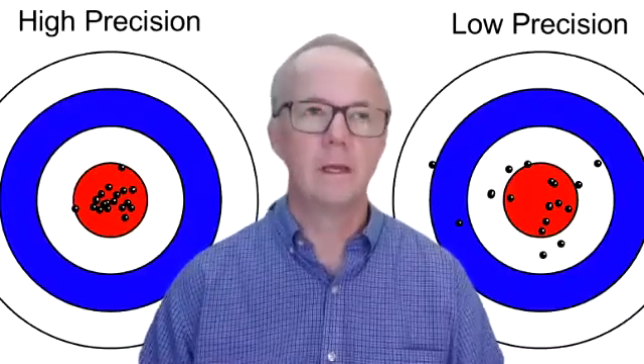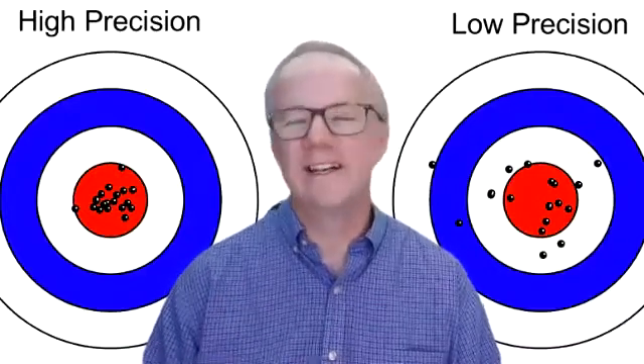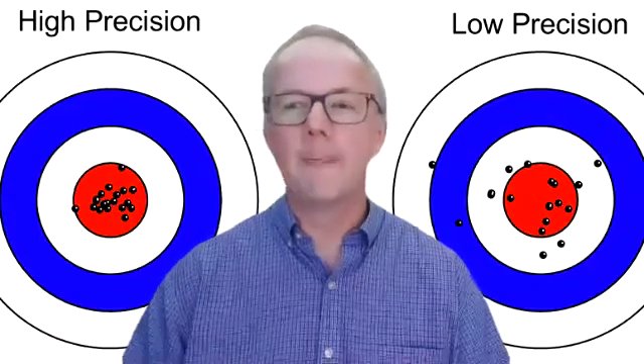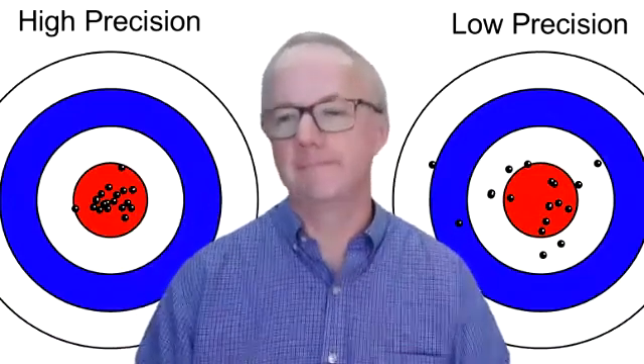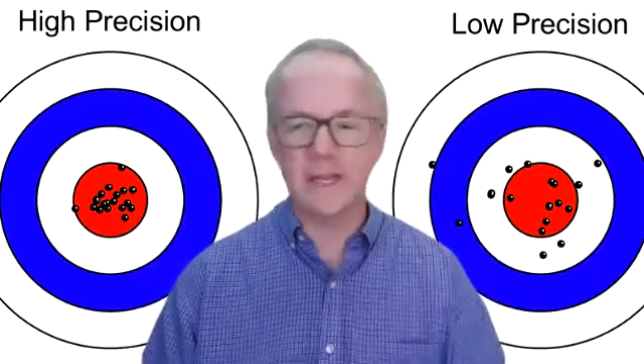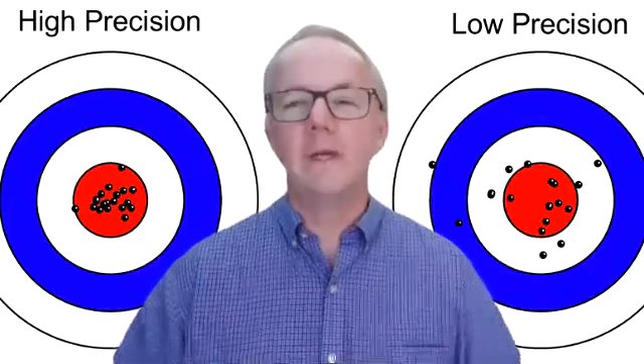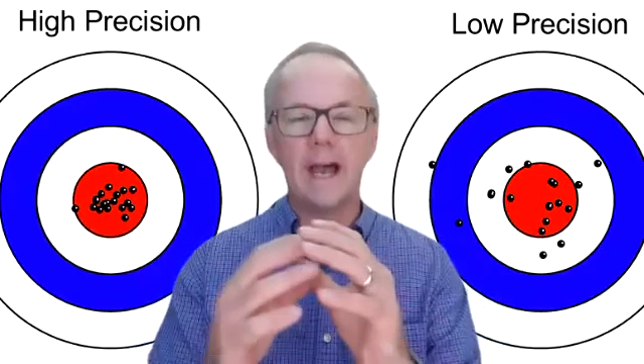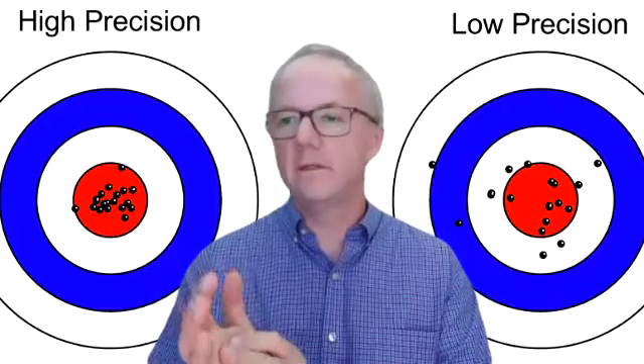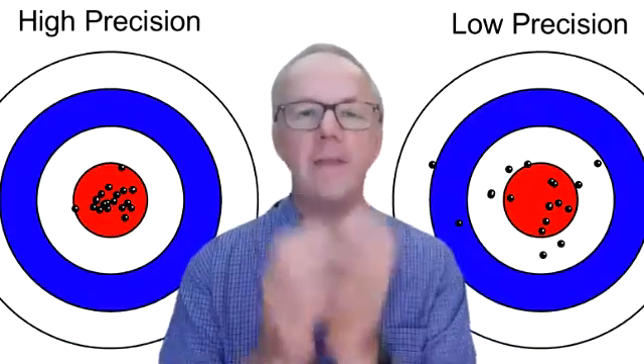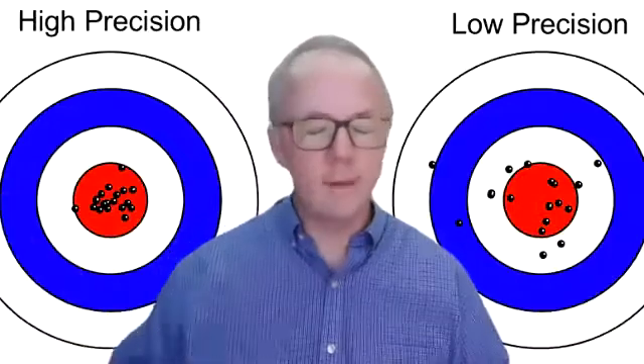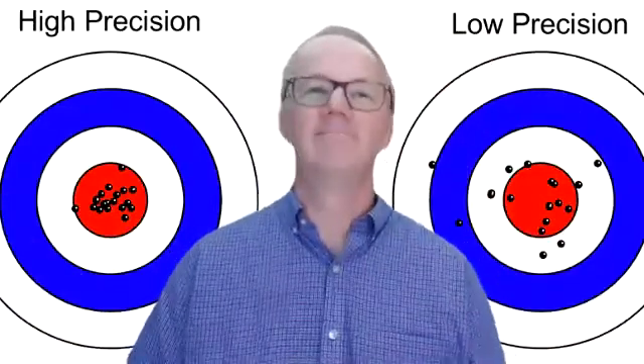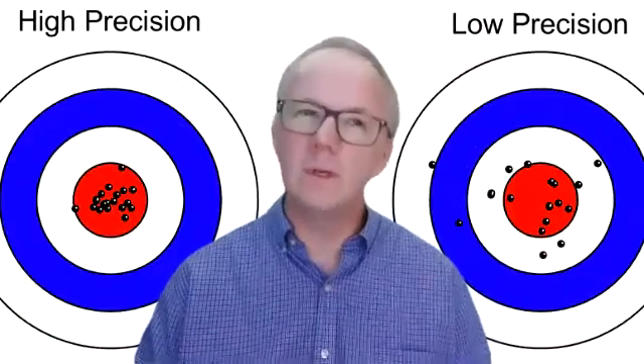To understand what precision means when they give you the precision results of the testing: the target value is the actual value from the equipment used to give traceability to national standards. When we talk about precision, we're not talking about how close to the target value — that's accuracy. Precision is about how well the results are clustered: when you repeat the test, do the results come together? Are they close together or all over the place?